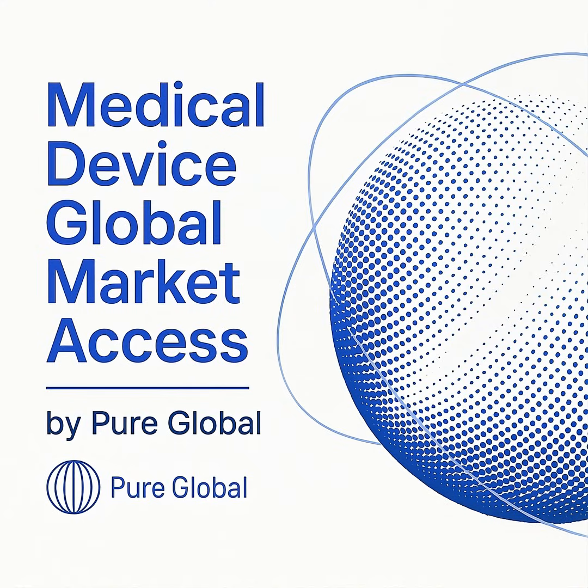With the removal of the loan license, the responsibility now falls directly on the manufacturer to provide clear information on the product itself. The new rule mandates that the label of any medical device sterilized by a third party must now include specific details. These are the name of the third-party sterilization facility, the full address of that facility, and the date of sterilization. This ensures complete traceability and transparency for regulators, healthcare providers, and patients, directly linking the device to its sterilization history on its packaging.